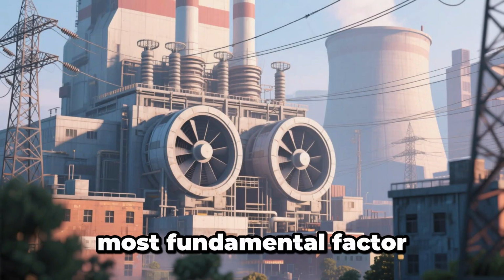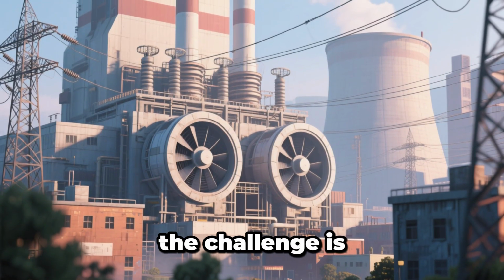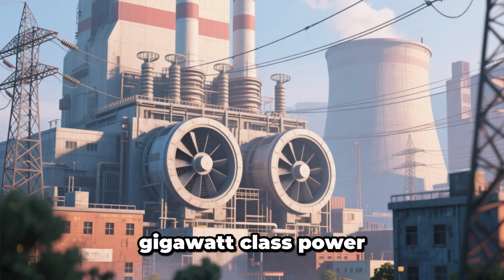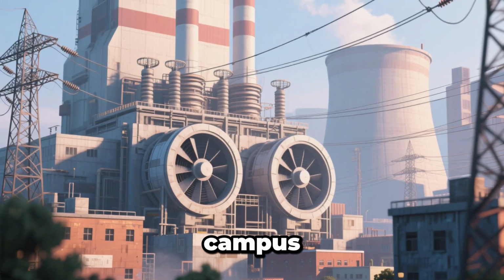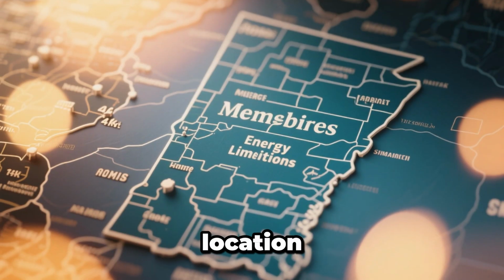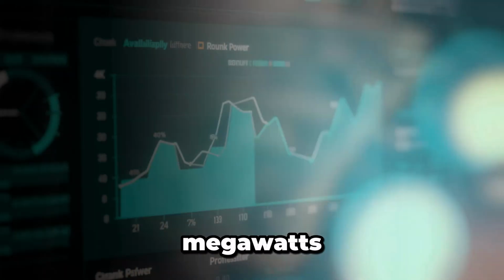The first and most fundamental factor is power. The challenge is delivering and stabilizing gigawatt-class power to a single campus. When scouting a location, the builders found that a major city like Memphis, Tennessee, could only spare about 50 megawatts. The requirement was nearly 1,200 megawatts.